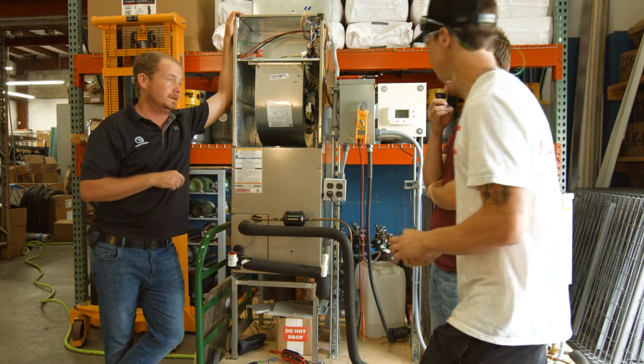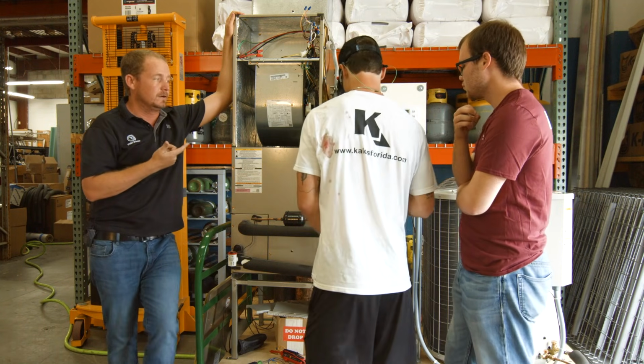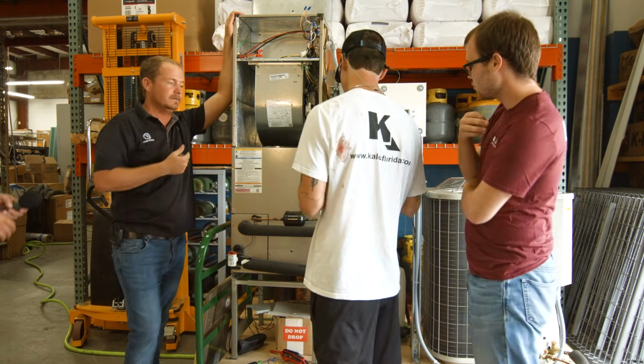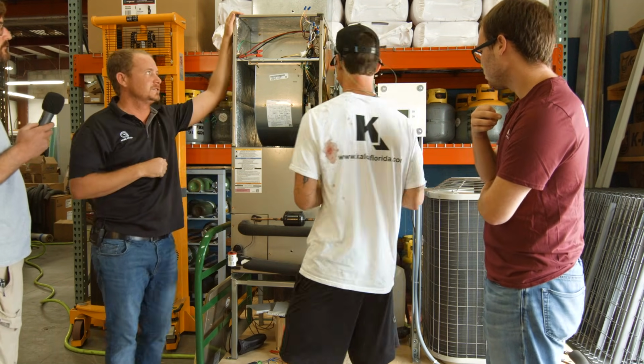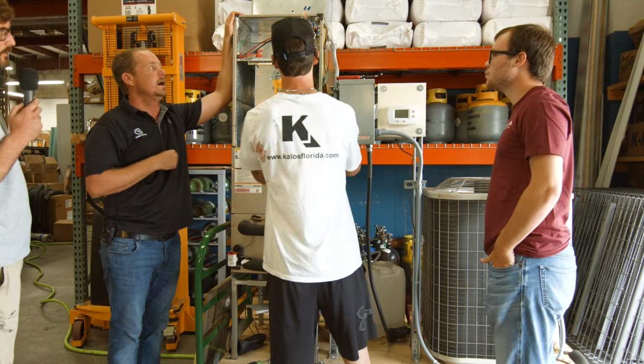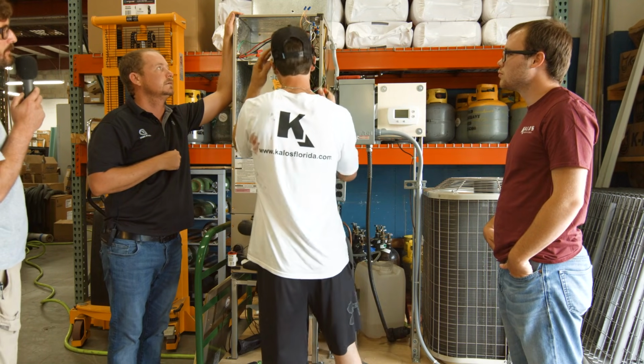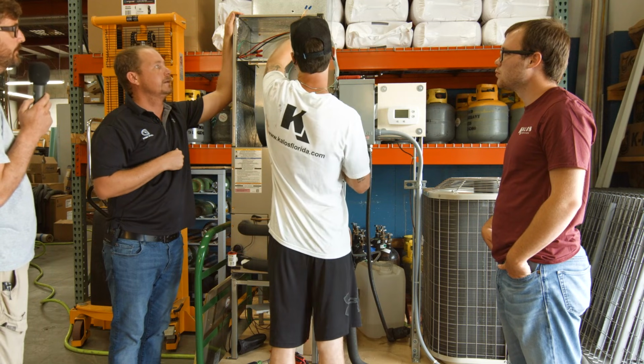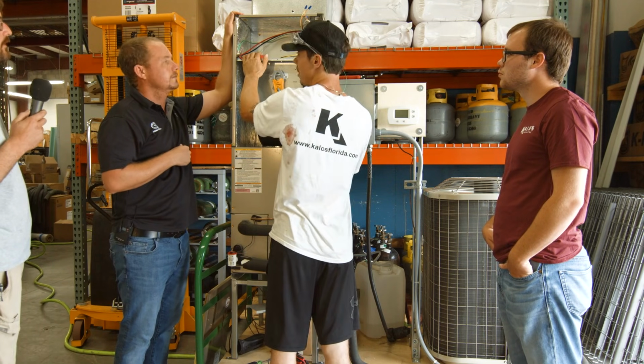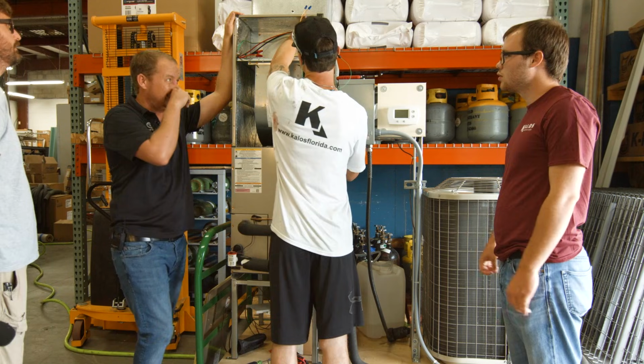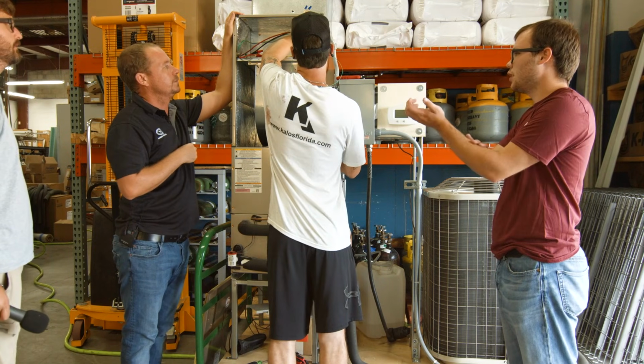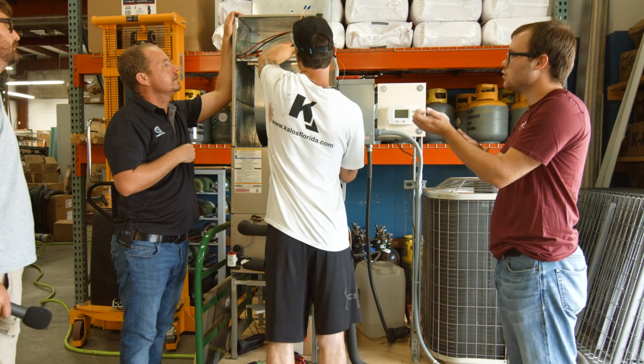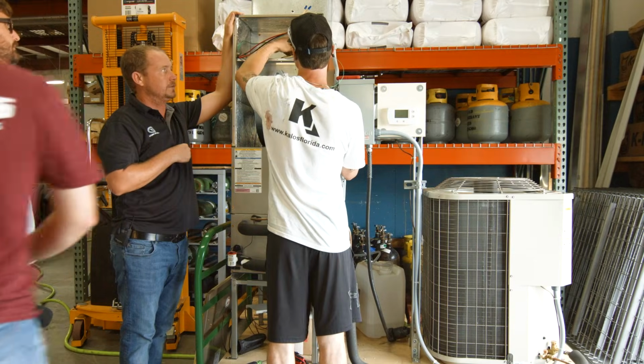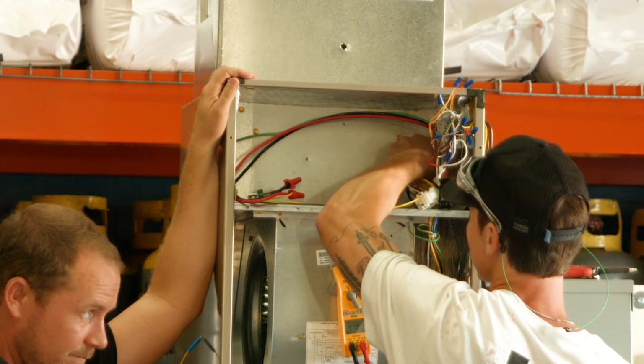Moving on to Eric's method here. So we're going to use the ohm meter. So we have it on ohm scale right now, right? You're always going to, there you go, exactly. Always double check. And so now, you're going to have to unplug both wires from the transformer, or else you get a false reading. Right, back feed. We already checked this, so we know power's off. We know power's off, exactly, yep. So you're pulling the wires off of the secondary, so both your common and your hot.